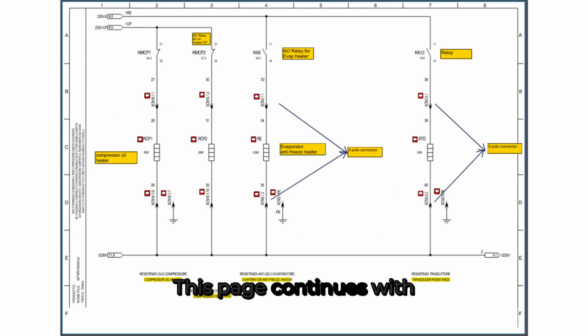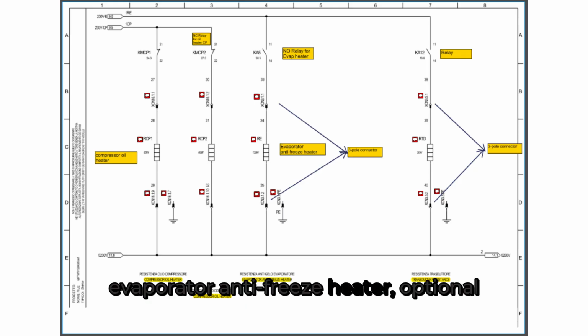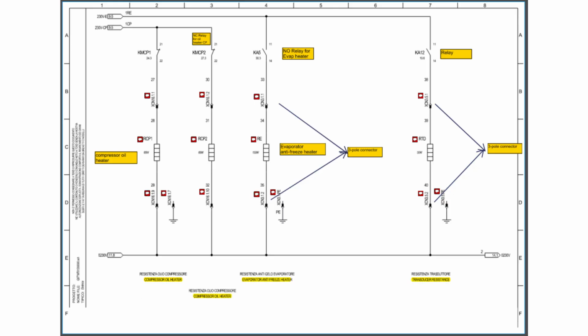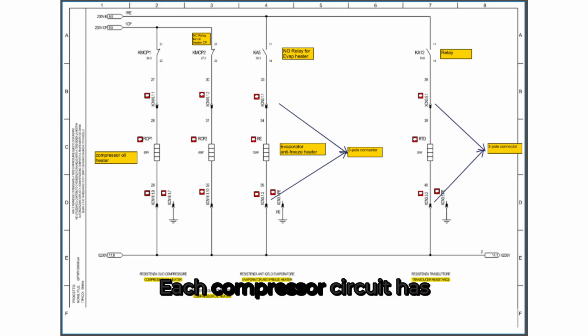This page continues with the 230-volt control power supply and focuses on the heating protection circuits, specifically for the compressor oil heaters and the evaporator antifreeze heater, optional desuperheater heat exchanger antifreeze heater. Starting from the left, the control power feeds into the compressor oil heaters, which are labeled RCP1 and RCP2. Each compressor circuit has its own dedicated oil heater.